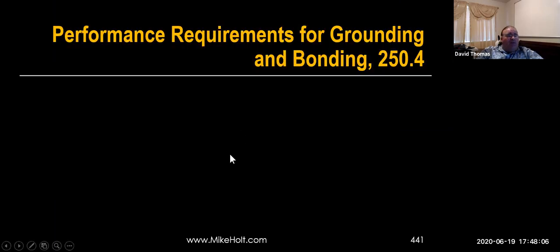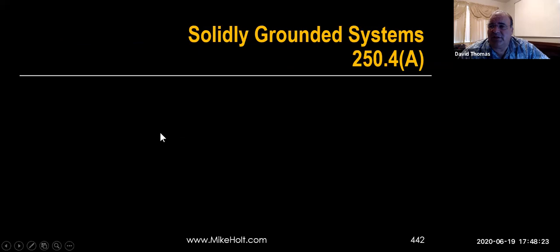And then, 250.4 is a very important section for me. I always end up reading this part because I think it gives us insight into why we ground and bond. Our systems are solidly grounded. What we're saying is that we take a solid ground to our system, and this is typically the systems we're dealing with out in the field. It's not the only ones, okay?